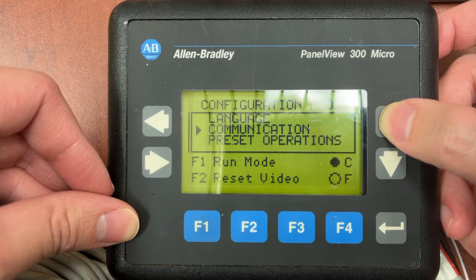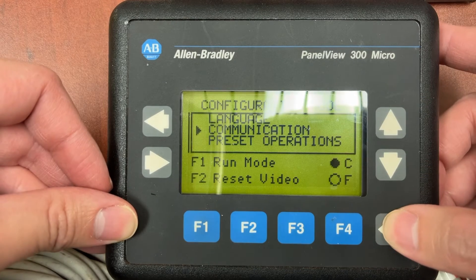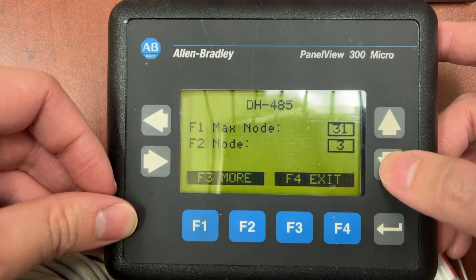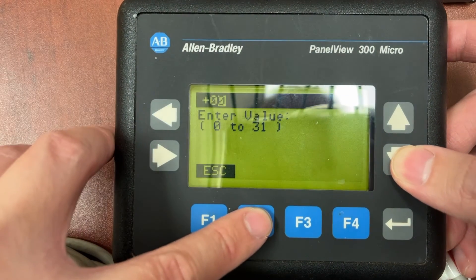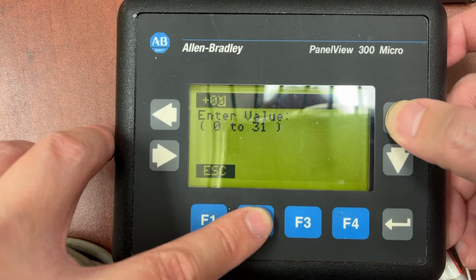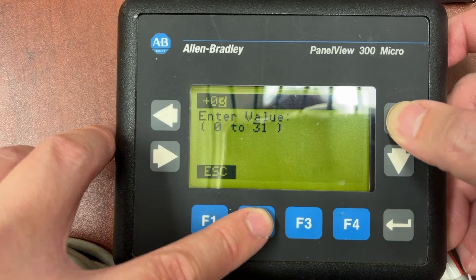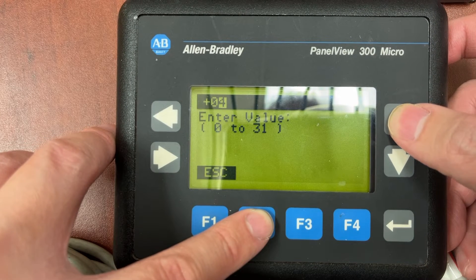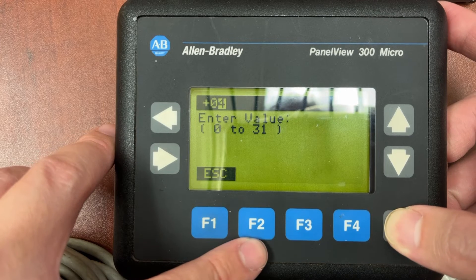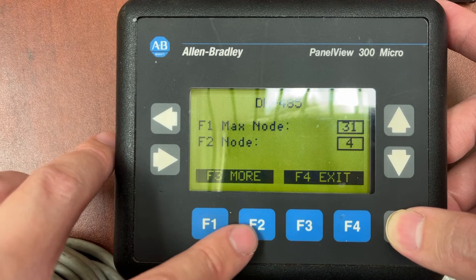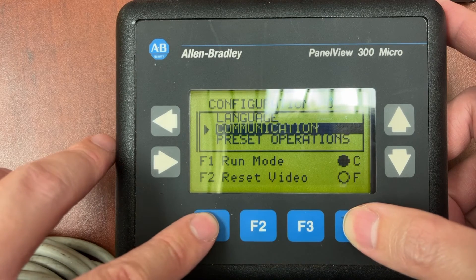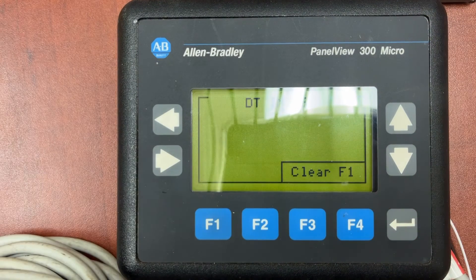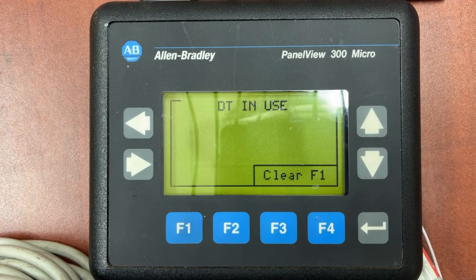Go to Communication and press F2 for Node. Make it Node 4, then press F4 to exit and F1 to run. No more communication error.